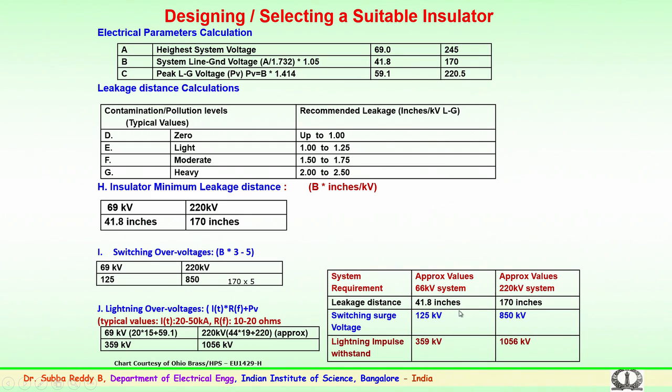These are the values for two different voltage levels. Similarly, for higher voltages — 400 kV, 765 kV and above — a similar pattern will be followed with other design considerations. The approximate values for both voltage levels, 66 kV and 220 kV, are: leakage distance 41.8 and 170 inches respectively; switching surge voltages 125 kV and 850 kV; lightning impulses 359 kV and 1056 kV. These values are for dry conditions.